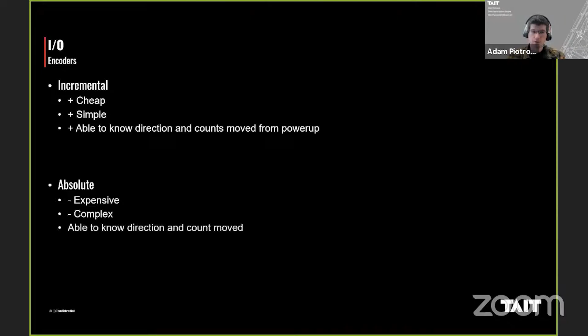Incremental encoders are simple—usually just a single disk of tracks—where an absolute encoder has more complexity to it. Incrementals are only able to know their direction and counts moved from power up, whereas with an absolute, you're able to know the direction and counts moved whether it's powered up or powered down. Once it powers up, if it was moved while powered down, you know that it did in fact move.